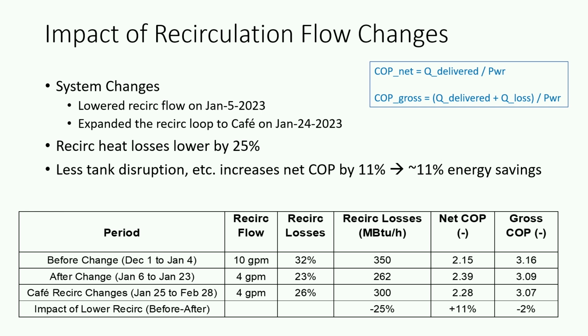But what we did see is that our net COP changed, or our COP when you just look at delivered divided by power. So when we changed our recirculation rate from 9 to 4 GPM, we saw a 10% higher efficiency, or a 10% change in energy use. And it's not explained by the change in recirculation losses. It's also less disruption to the tank. So it's several things going on. It shows the importance of these things that nobody pays attention to in a multifamily hot water system, kind of a big impact.